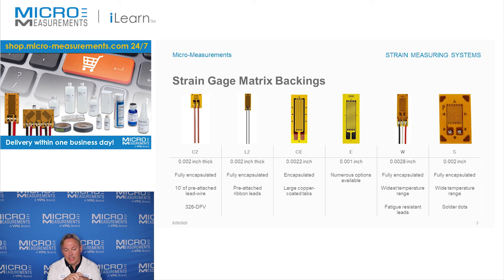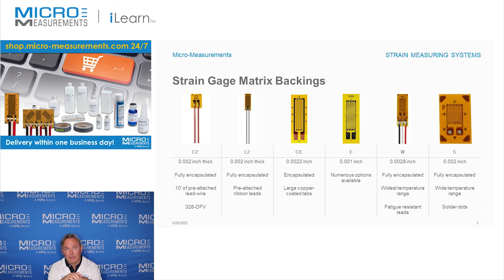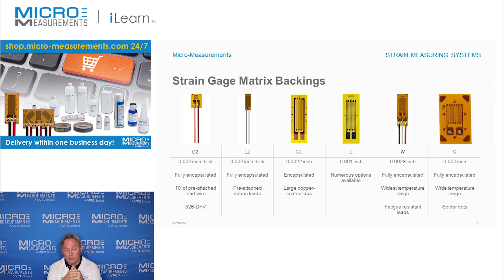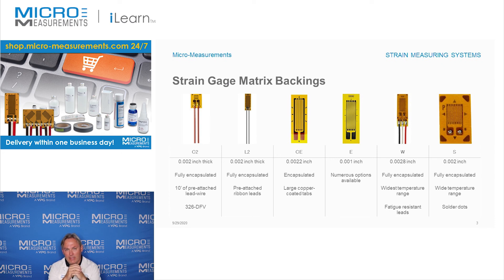The W backing has beryllium copper lead ribbons, which also help to enhance the fatigue life of the strain gauge. The S backing is the same glass-reinforced epoxy phenolic material as the W, but the difference is that it has solder dots instead of beryllium copper lead ribbons. Some customers prefer the lead ribbons, some prefer the solder dots — it's largely a personal preference. The W backing can go a little higher in temperature; the S backing is derated somewhat because the 570 solder dot sets the upper temperature limit. Conservatively, we rate the S backing at about 500 degrees Fahrenheit.